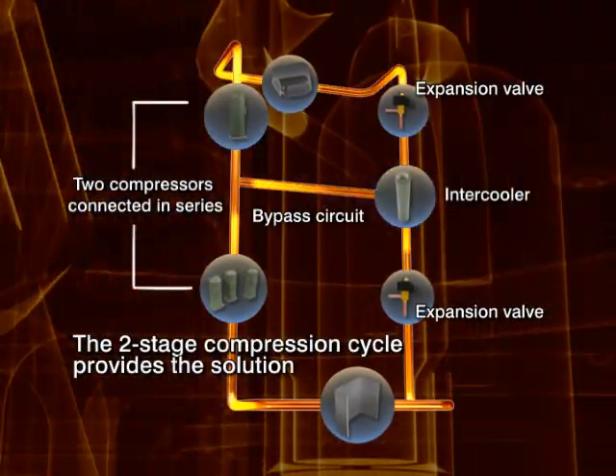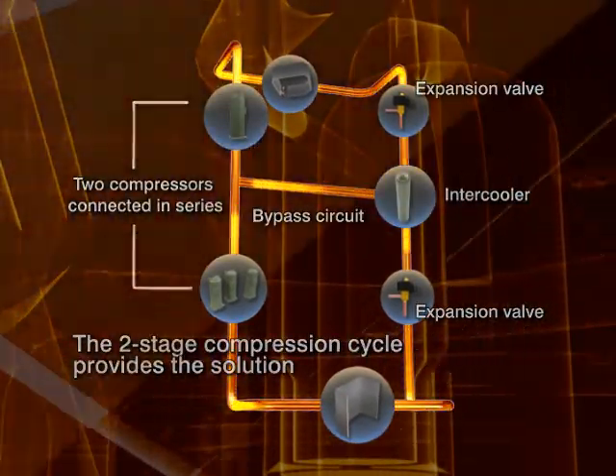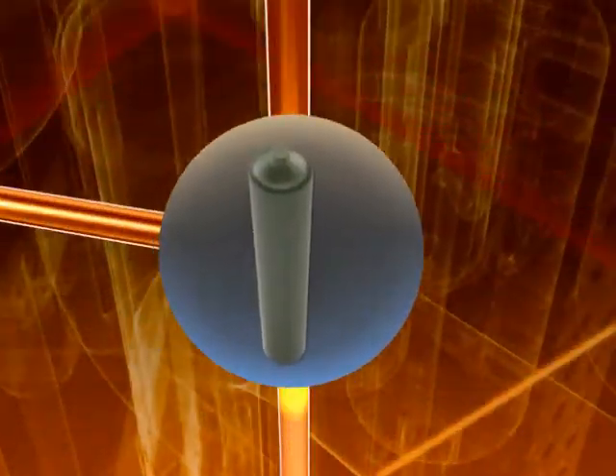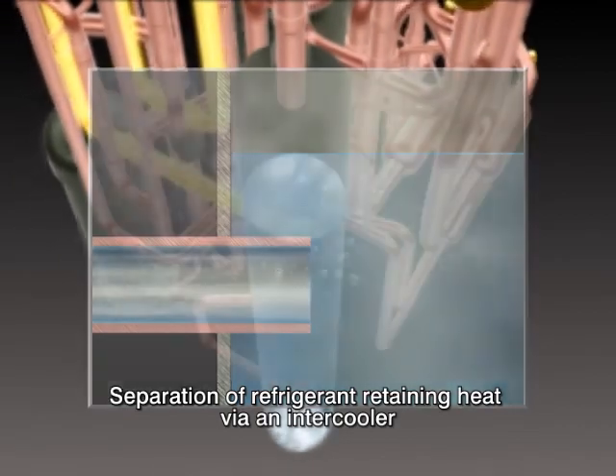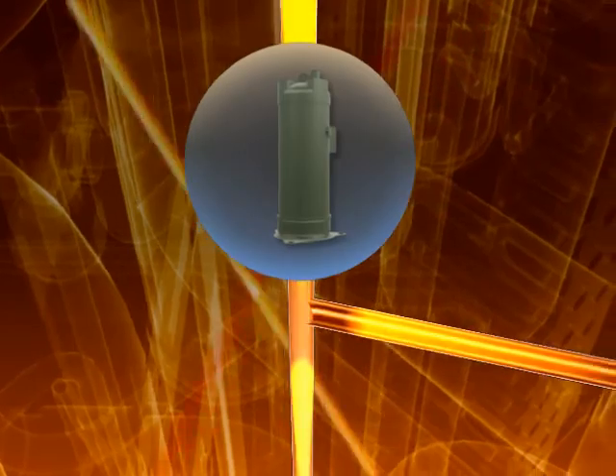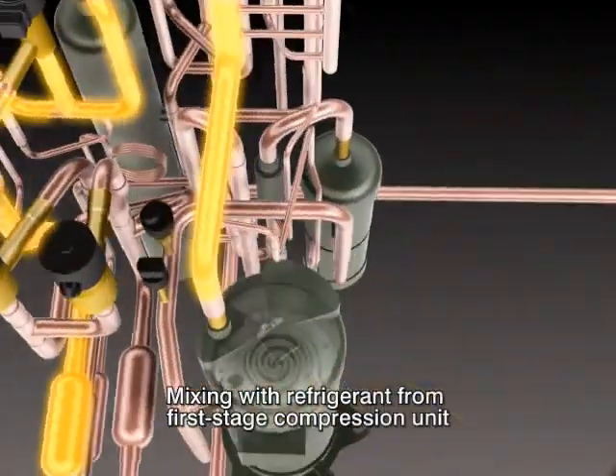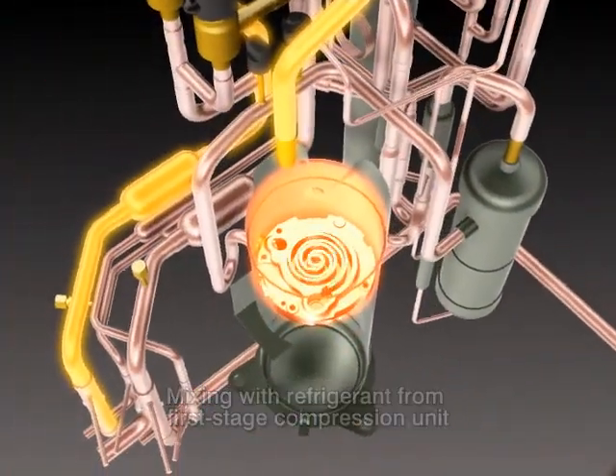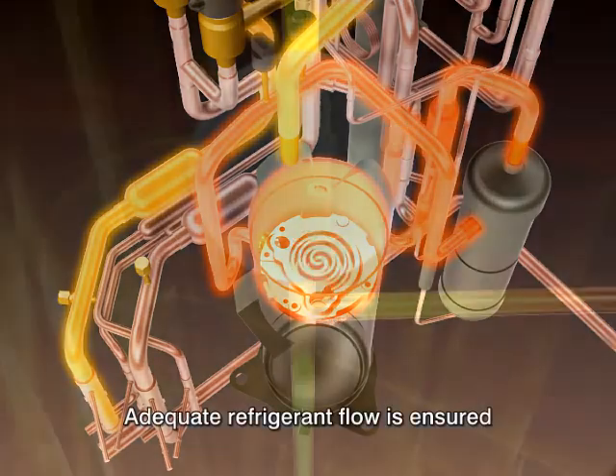Daikin's unique two-stage compression cycle solves this problem. In heating mode, refrigerant retaining heat is separated by an intercooler and is then channeled through a bypass circuit, mixing with refrigerant from the first stage compression unit and ensuring adequate refrigerant flow.